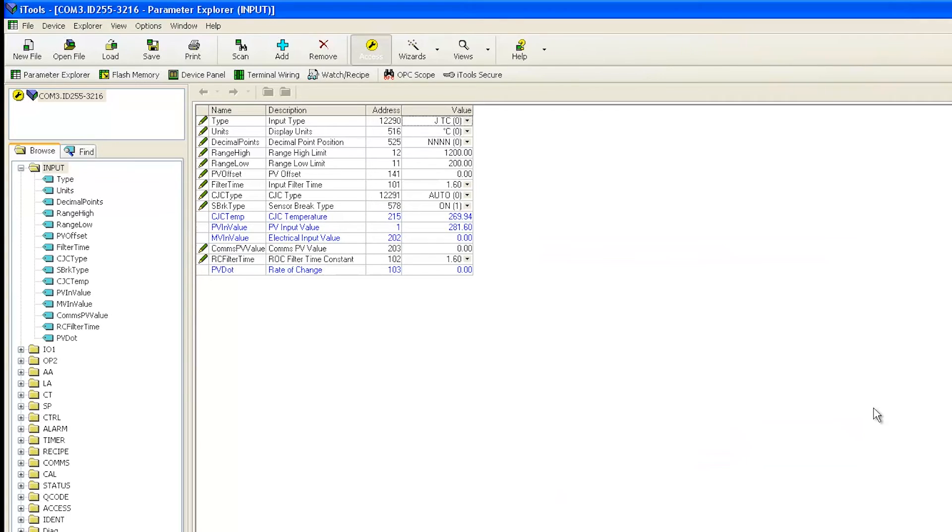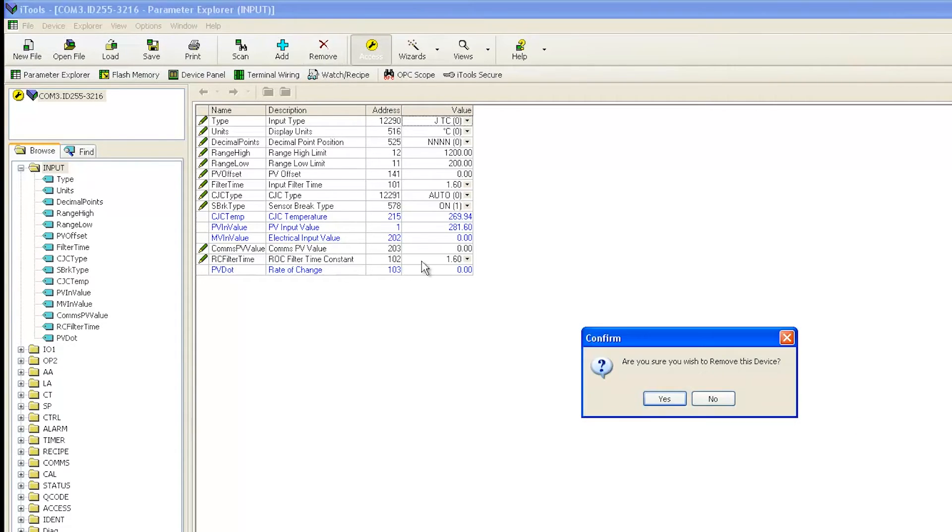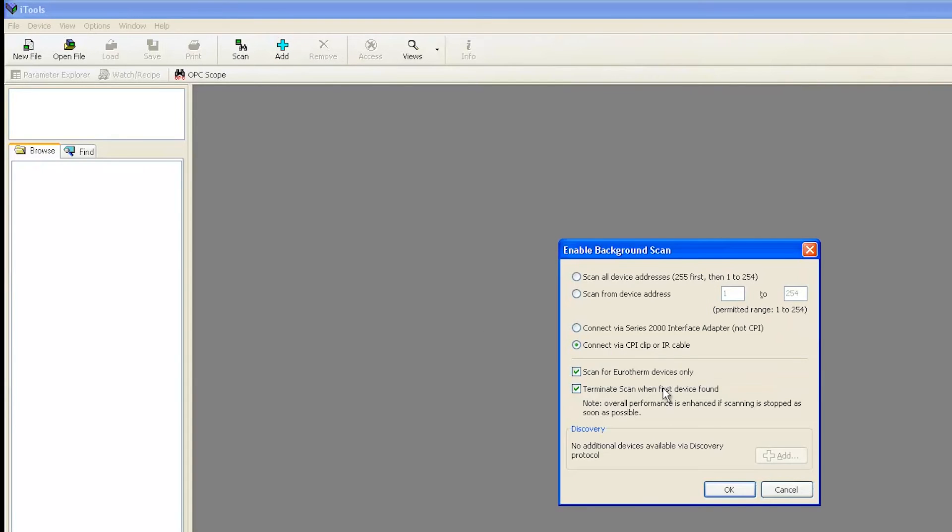When finished, click Remove to safely disconnect the controller. Once iTools finishes removing the controller, you can disconnect it from the clip and connect the new controller in the same way you connected the first. It is important to note that both controllers must have the same exact hardware model code.